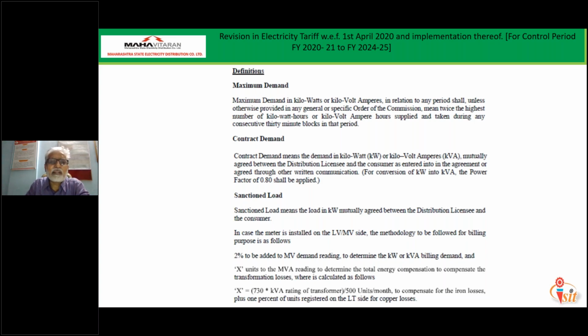The contract demand is the mutual agreement between the distribution company and the consumer. Suppose the consumer wants a contract demand of up to 100 kVA. This is the agreement that continuously that much is allocated to that consumer, so they can consume electricity up to 100 kVA. But if the consumer consumes more than 100 kVA, they get an additional penalty per kVA, say 450 rupees or 411 rupees, for whatever is used above the contract demand.